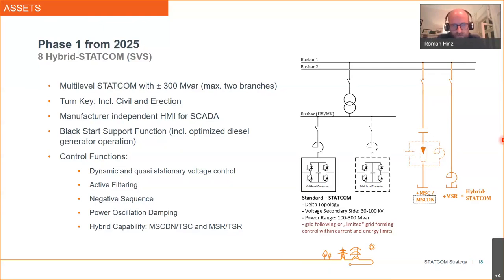These are a few steps in the direction of a grid forming control, because grid forming control has several packages which it has to fulfill. For example, negative sequence control and active filtering are some of them, and also power oscillation damping and so on. And as I have told you, a really important thing is that we can operate, and we also tender right now, mechanically switched impedances like capacitors or reactors in the same substation.